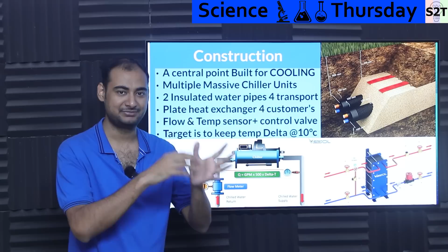Like, let's say you have vaccination storage. In that sort of scenario, it would be better if, instead of dumping the heat into ambient air, you dumped heat into a cold liquid that is, let's say, 5 degrees Celsius or 6 degrees Celsius, because again, those ultra low temperature vaccination cabinets require minus 80 degrees Celsius. So helping them matters. But again, you do have to talk with the district. It's like, hey, you cool with this? And so that's the plate heat exchanger part. You get the cold liquid, you circulate it via either fan coil unit or air handling unit, you get your cooling.